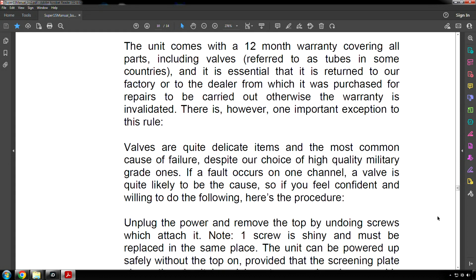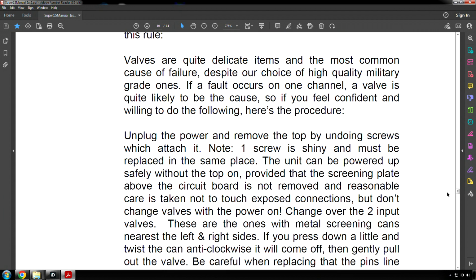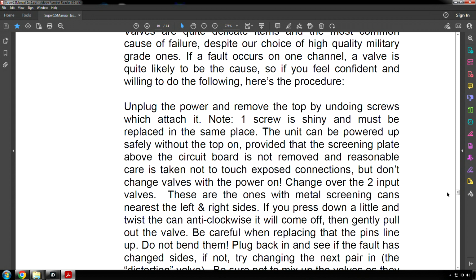If a fault occurs on one channel, a valve is quite likely to be the cause. So if you feel confident and willing to do the following, here's the procedure. Unplug the power and remove the top by undoing screws which attach it. Note, one screw is shiny and must be replaced in the same place. The unit can be powered up safely without the top on, provided that the screening plate above the circuit board is not removed and reasonable care is taken not to touch exposed connections. But don't change valves with the power on.